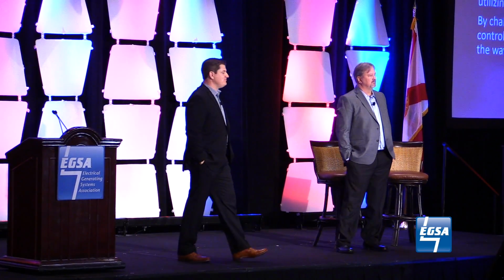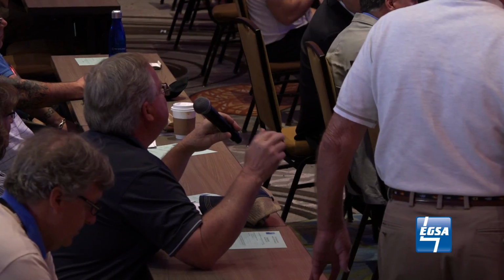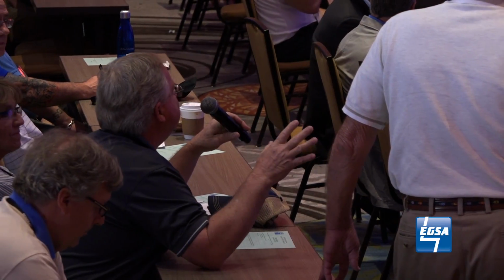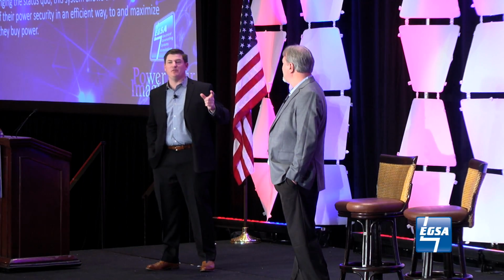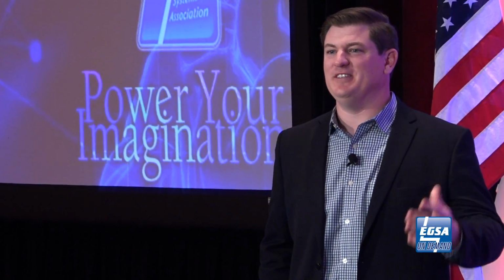Two questions. So what is the redundancy level? I saw 2 utilities, 23 generators. What's the N plus? So this specific plant, we're 100% for the plant. This particular plant has 4 5,000 horsepower compressors on the residue side that use a technology that's basically dual drive. So they have a gas engine and electric motor. So they get those off of utility a little bit differently than we would have done it.